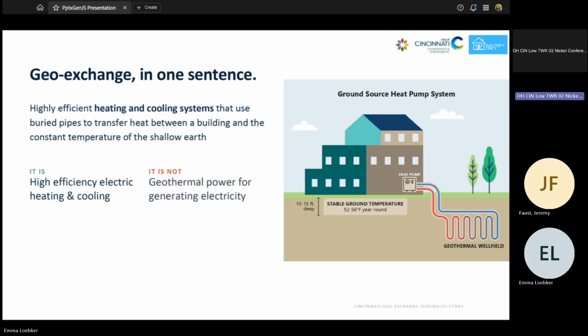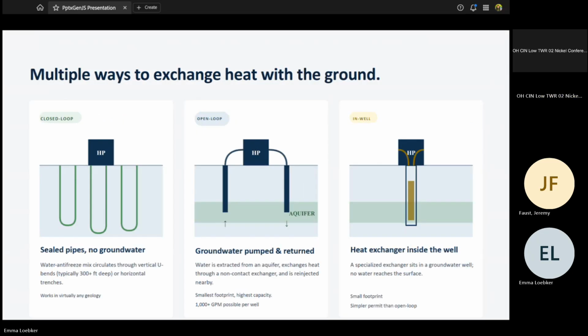Let's go to the next slide. This is just a graphic of the three primary types. You've probably heard of a closed loop system, where you drill boreholes down 300 to 500 feet deep into soil or rock, put in a U-bend loop, and grout that loop. It's about an inch diameter HDPE piping, which gets networked and headered together in a system and back to the mechanical room.